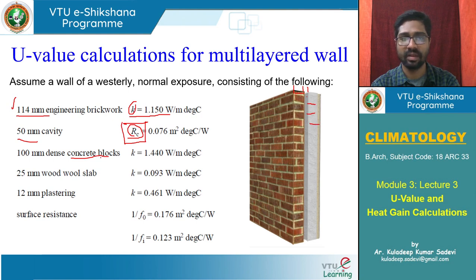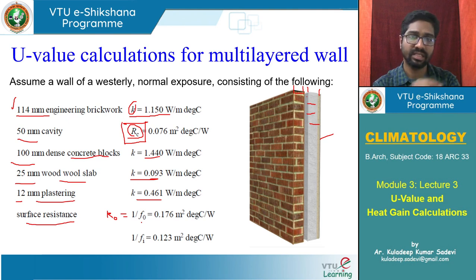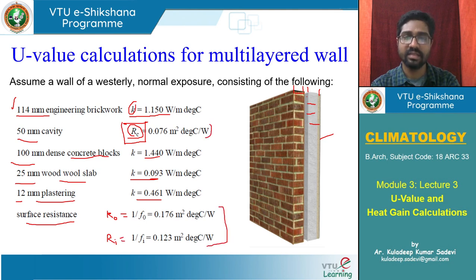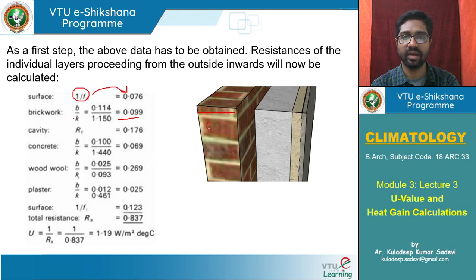Then we have concrete blocks with conductivity and thickness giving R = 0.069 m²·K/W. Then wood wool slab with R = 0.269 m²·K/W calculated from conductivity and thickness. Then plastering with conductivity and thickness again. Surface resistances are given directly — the outdoor surface resistance R₀ = 1/F₀ (surface conductance), and inner surface resistance Rᵢ. Three layers have direct R-values; other layers require conductivity and thickness.